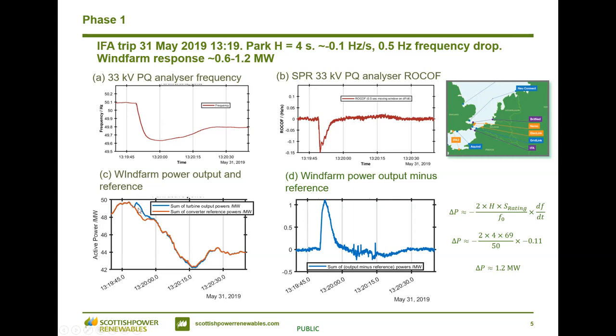response. One thing I need to highlight as well: to achieve that inertia response, we had to run the turbines curtailed by more or less 250 kilowatts, because the energy has to come from somewhere to provide the inertia. So through that period of testing, we ran the wind turbines curtailed.